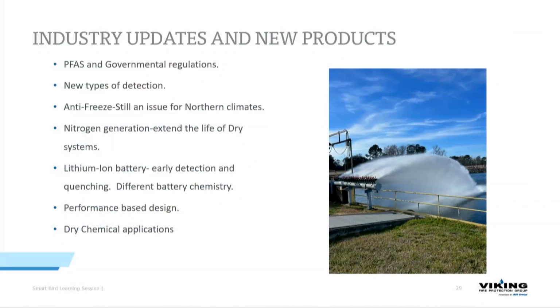So, lithium-ion battery, early detection and quenching. The coolest thing that I learned about in the last 2 weeks. So, rise in heat cabling. Basically you have cables that can determine the rise in temperature, 10 degrees, 15 degrees, whatever you want to set it to be. So in the EV battery market, pulling EV batteries off the end of the assembly line, putting them on trays and racks, and it's all automated. There are these heat cables running all throughout this racking. If they detect that one of these trays is starting to have a rise in heat, they have the robot that put it there go back, grab it, pull it to a safe location in the facility, dump it in salt water, and they're done. So we've prevented a fire without ever having a fire. Those are some of the really cool things in our industry right now, where we're getting to the fires before they happen.